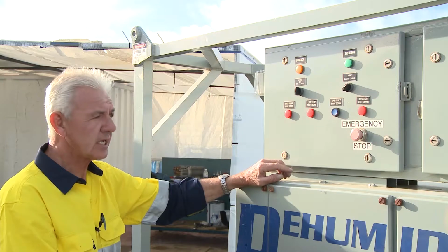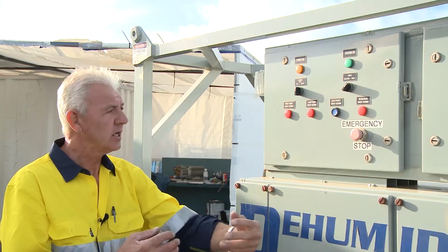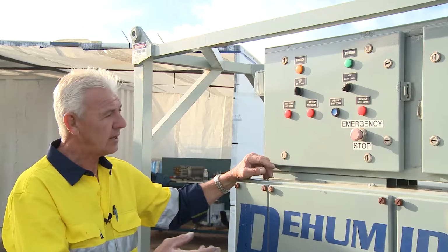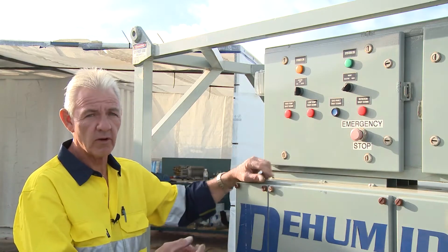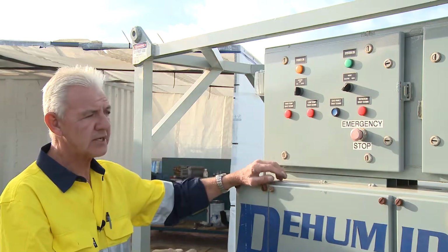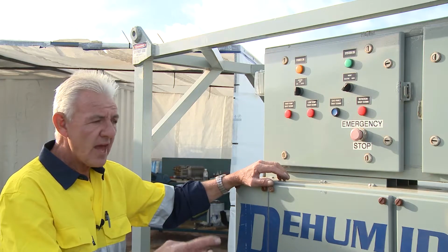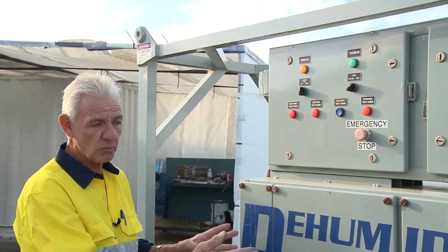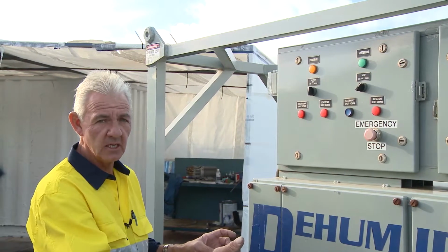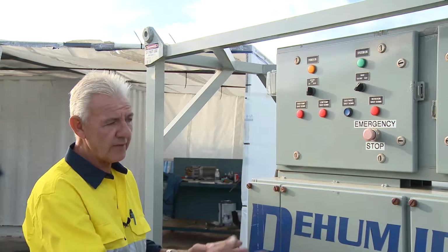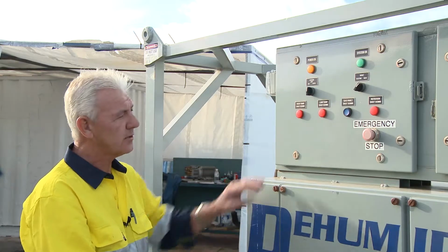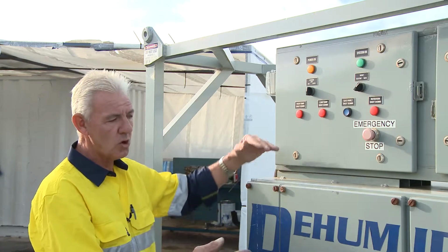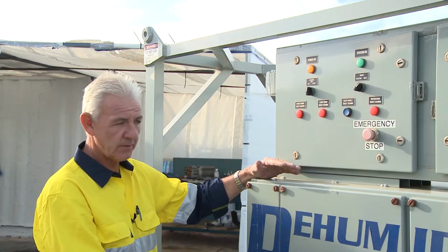The low temperature shutdown is on the other side of that scale. So if, say for example, we have an influx of air and it can't cope with that volume of cold air, you'll have a low temp shutdown. Predominantly that is just a safety measure to keep this particular desiccant wheel and its heating capacity at a reasonable level that the machine can monitor. So is it a common occurrence? No, it's not. It's just a fail-safe in relation to what is processed as far as the air is concerned.